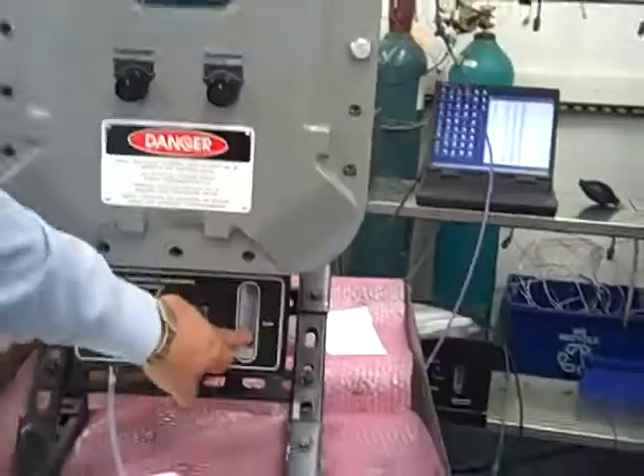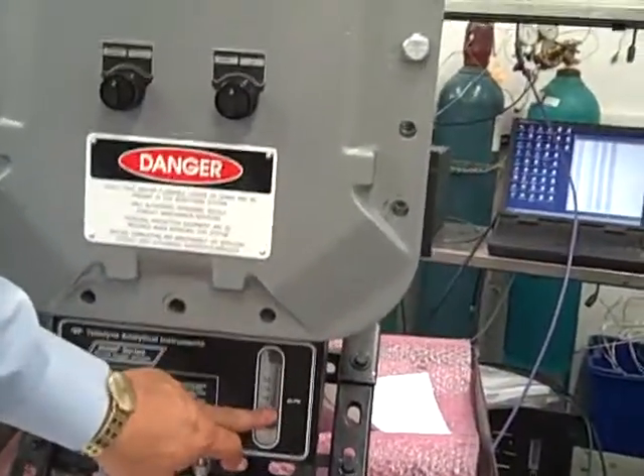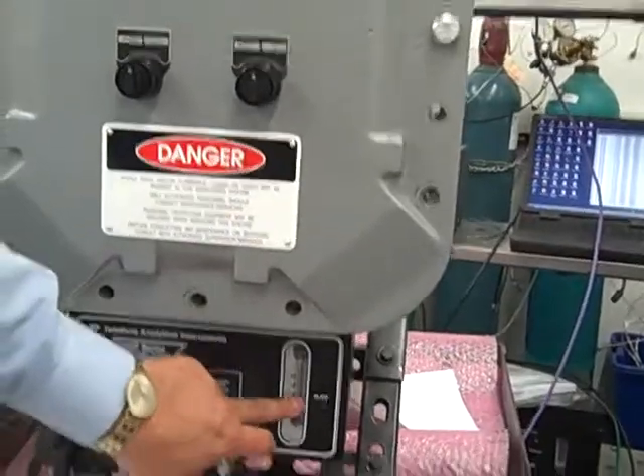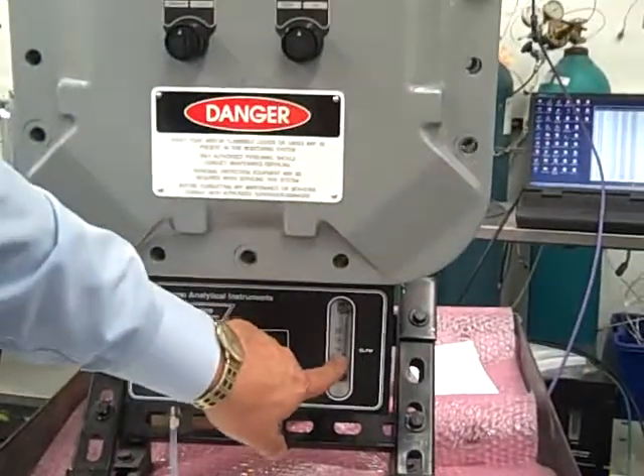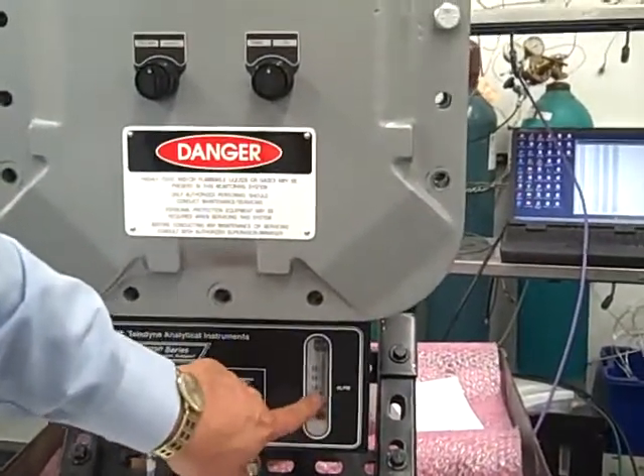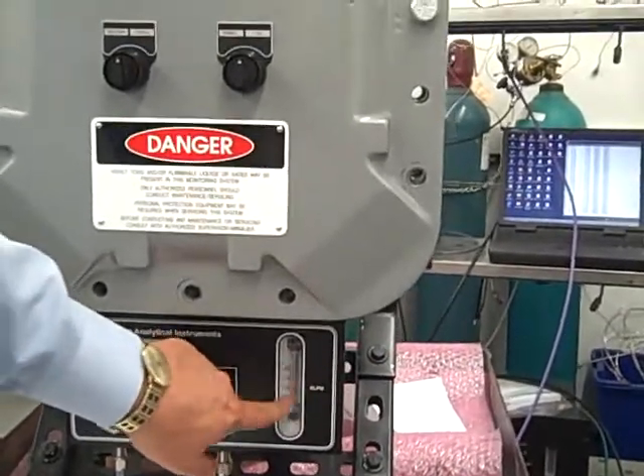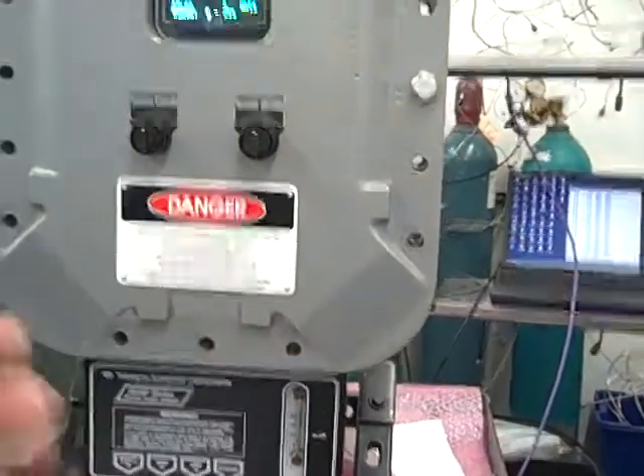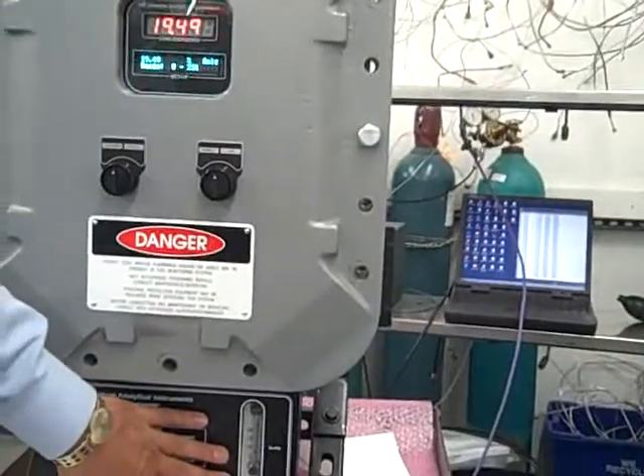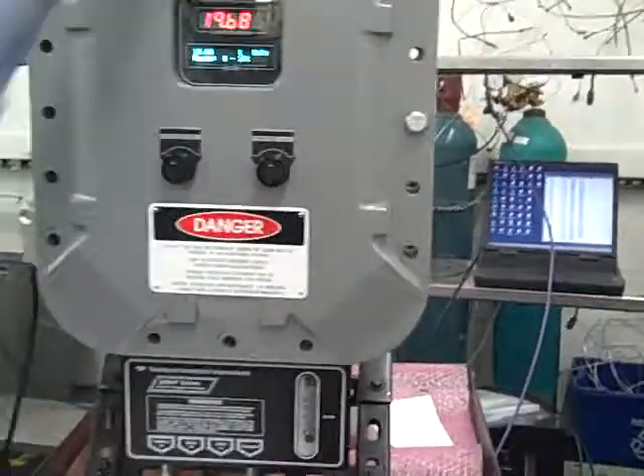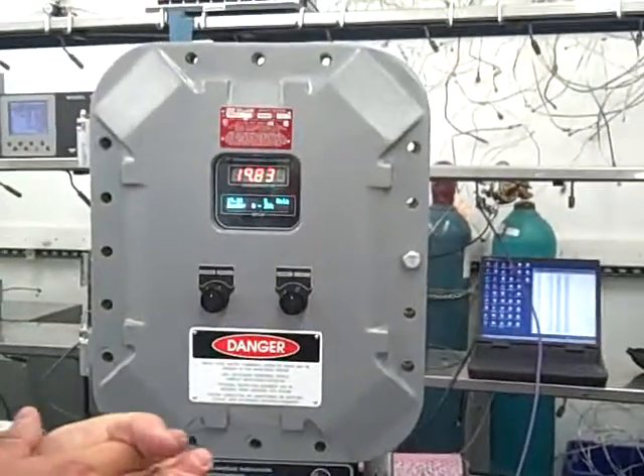Make sure you've got flow through the unit, of course. The unit is pretty much flow insensitive, but you want to keep a constant flow if you can, typically of about 1 standard liter per minute or so, but anywhere in there is okay. And one neat thing about the micro fuel cell technology, which these units use, is the sensors are flow insensitive.